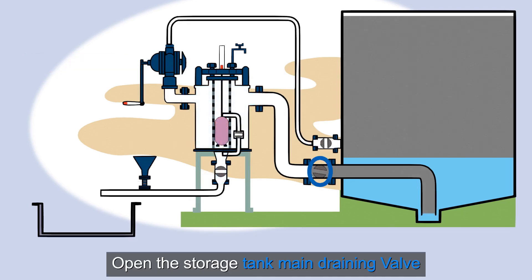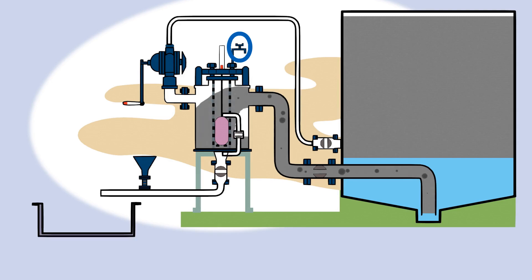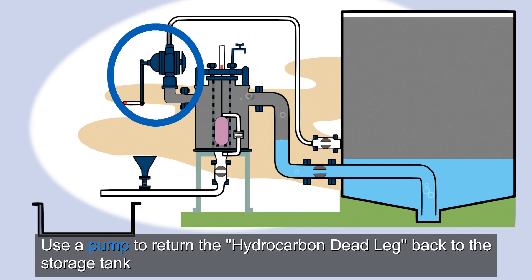Open the storage tank main draining valve. For the first draining only, release the trapped air using the vent valve. Close the vent valve once the air has been released and liquid begins to flow. Use a pump to return the hydrocarbon dead leg back to the storage tank.